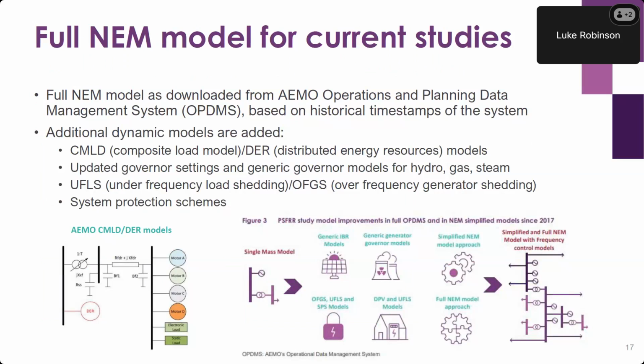Okay, so this is discussing the full NEM model in a bit more detail. If we're studying risks that are present in the current system, we can generally use the full AEMO NEM model fairly easily. From the AEMO Operations and Planning Data Management System, or OPDMS, as we might refer to it, we can download PSSE cases that are aligned with historical dispatches from the system. We have half-hourly intervals where cases can be downloaded, and these PSSE cases will align with the generation, load, interconnector flows, machines online, and many other factors for the time specified.